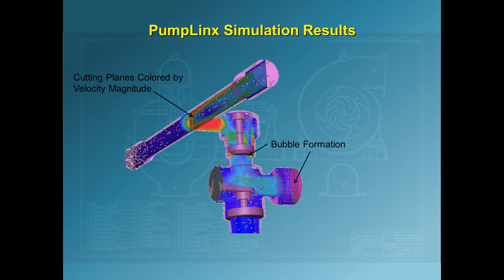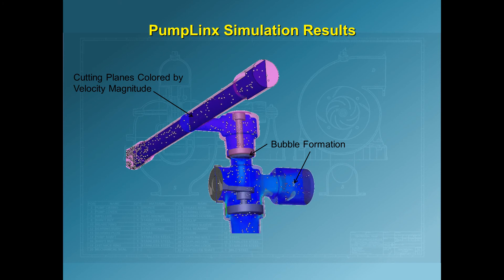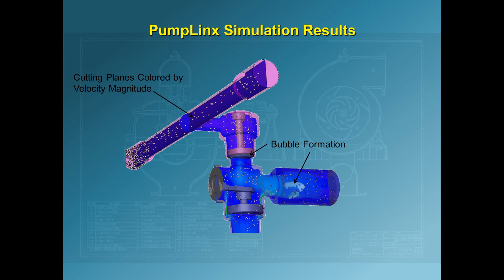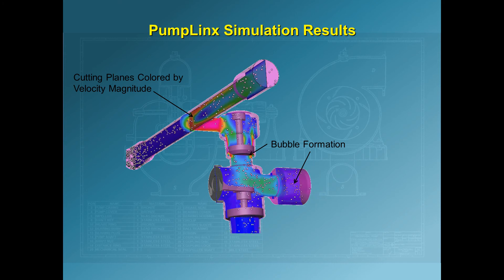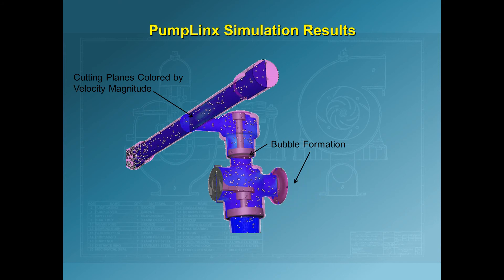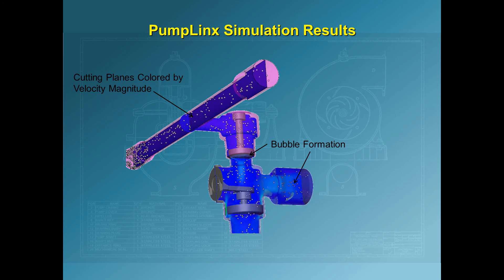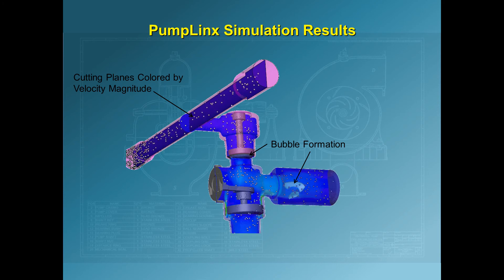During the compression stroke, the inlet valve closes and the outlet valve is forced open by the fluid pressure. In this simulation, PumpLinx predicts the motion of the valves using the force balance of the pressure integrated over the valve surfaces, the valve mass, and the restoring spring force.